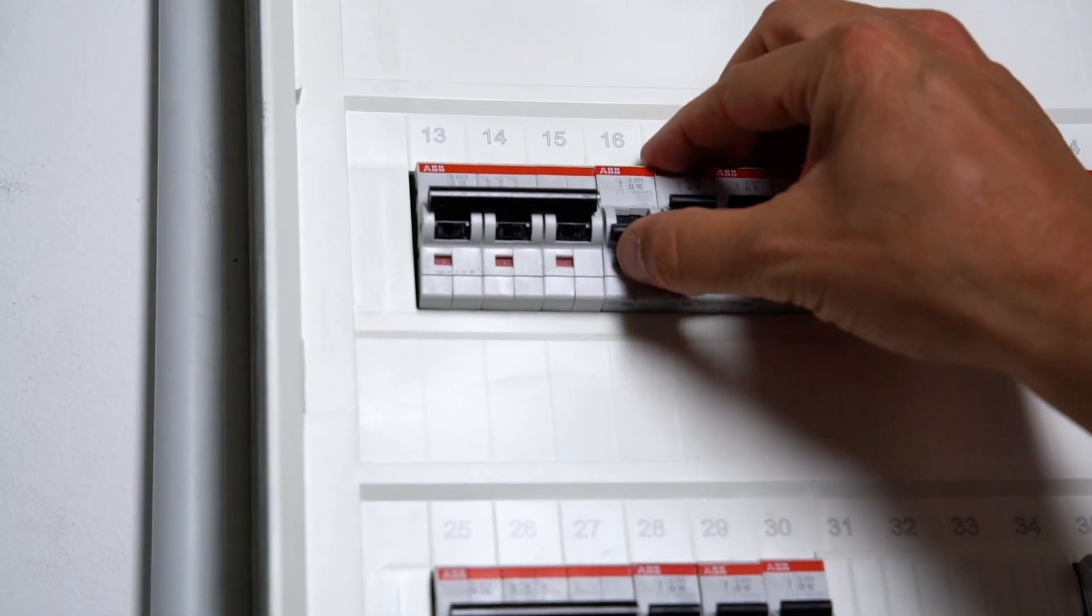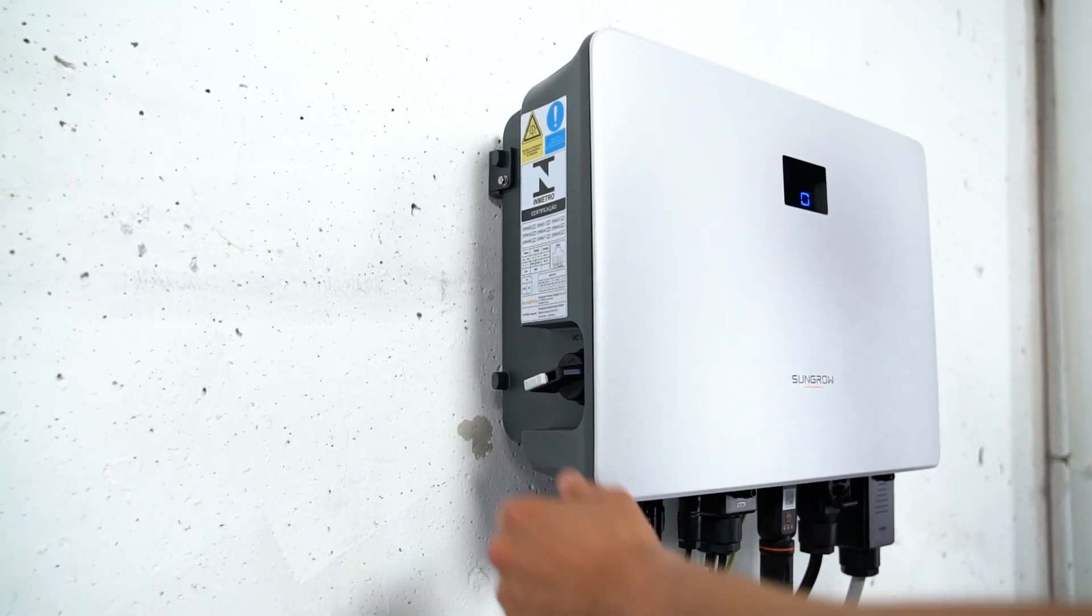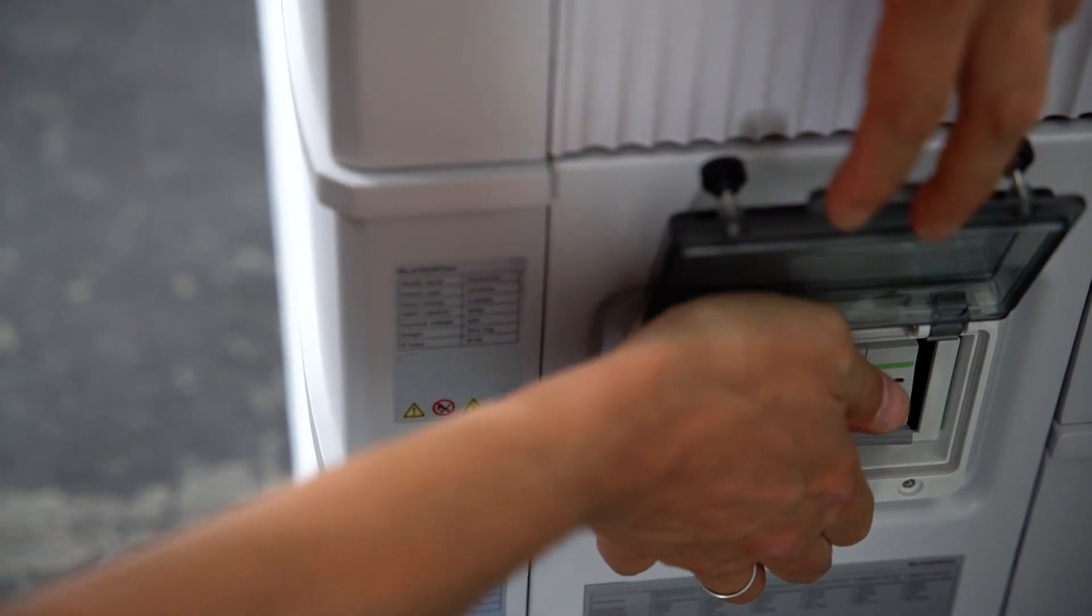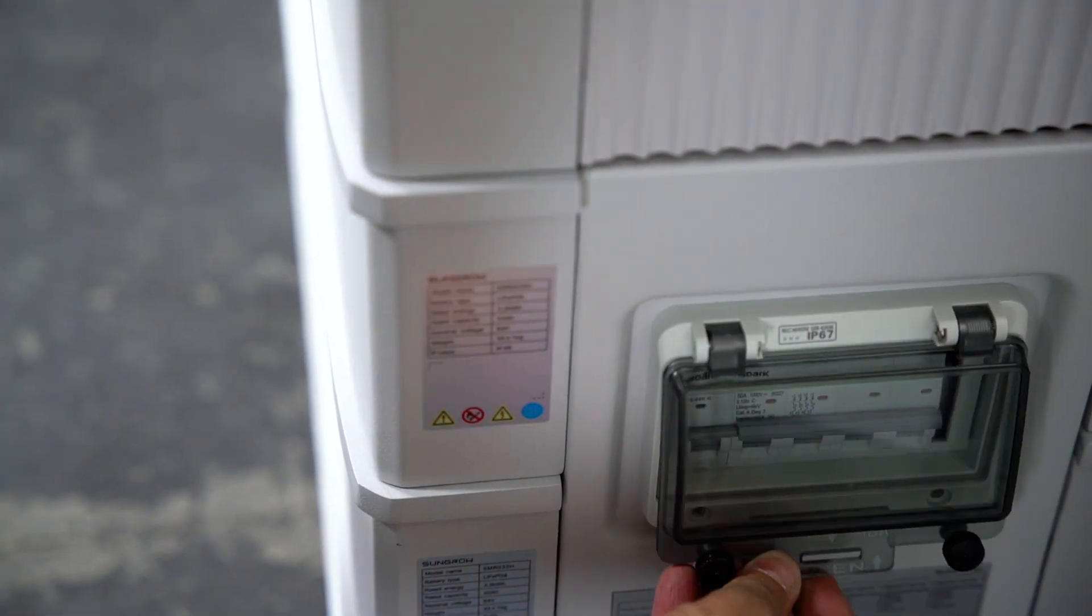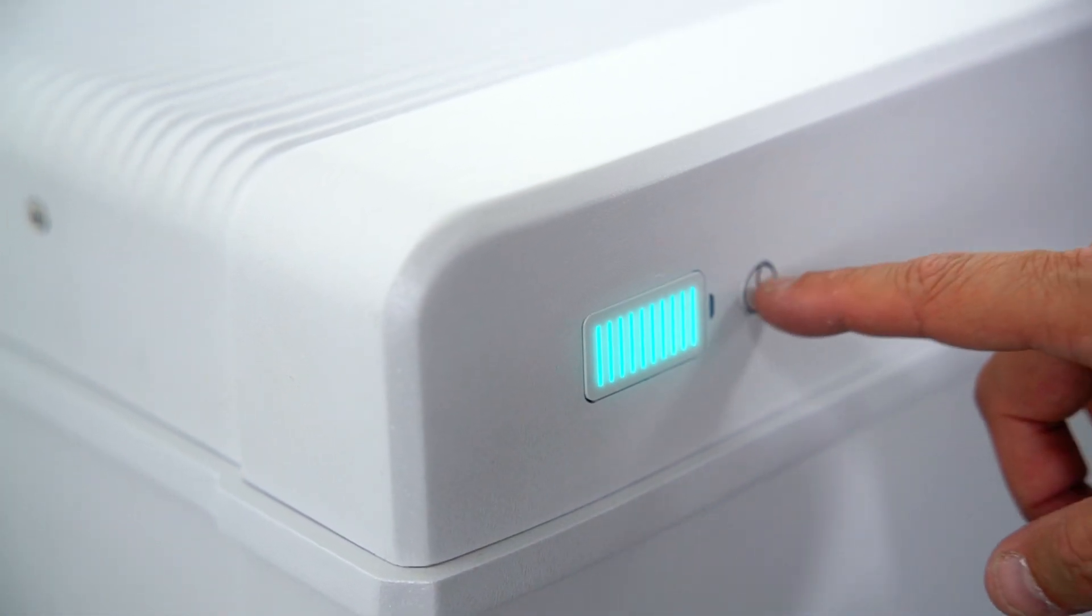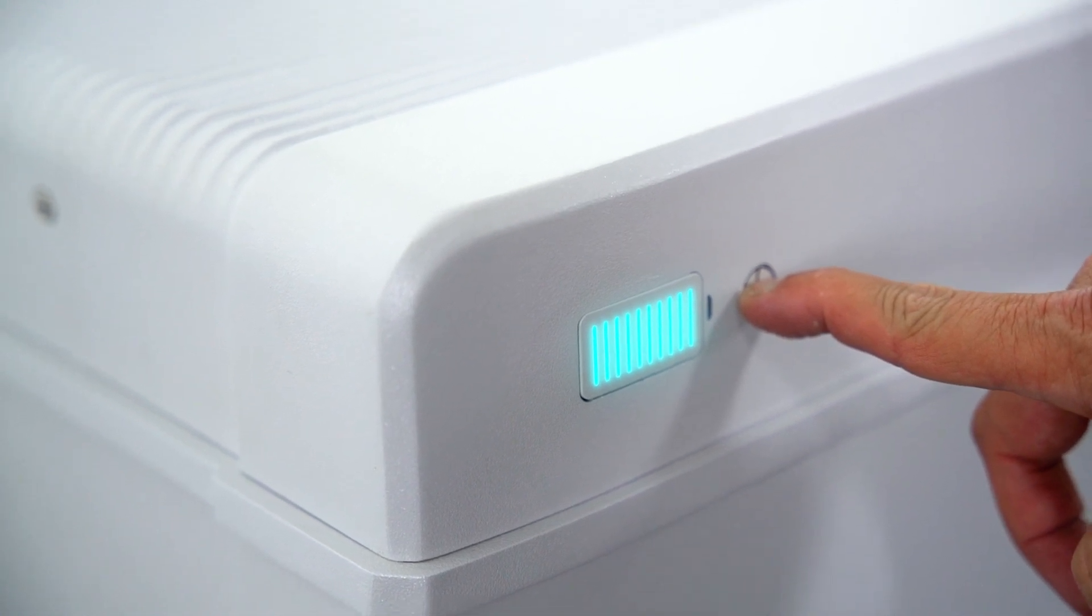First, switch on the AC circuit breaker and second, the DC circuit breaker on the left side of the inverter and on the right side of the battery. Wait for about 10 seconds till the status LED on the battery starts blinking. Press the power button once. When the light shines continuously, the battery is ready for use.